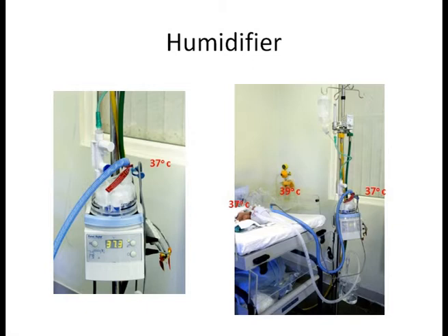So overall, the gas coming from the humidifier is going to be at 37 degrees Celsius with 100% relative humidity, gets heated in the inspiratory limb to 39 degrees with a relative fall of humidification, and gets to 100% relative humidity, temperature of 37 when it goes to the patient. And there is going to be some condensation in the expiratory limb, which you can see as droplets of water in the expiratory limb. But when these droplets fall into the bubble chamber, it is not going to lead to increased water level.